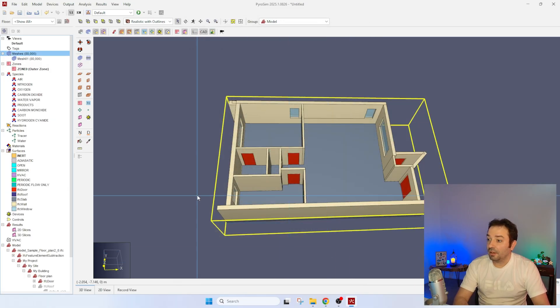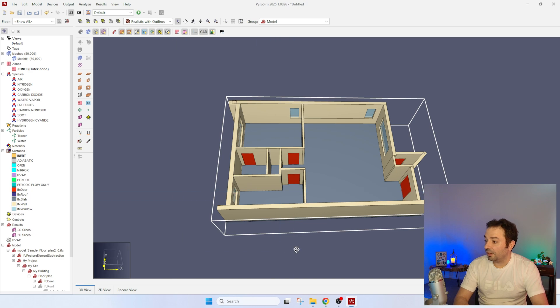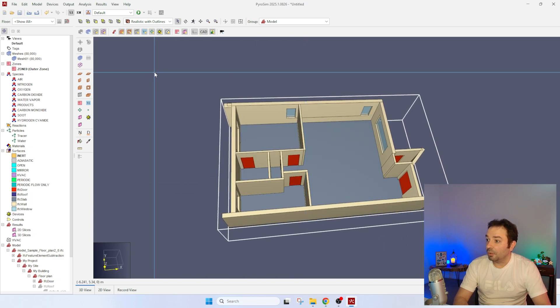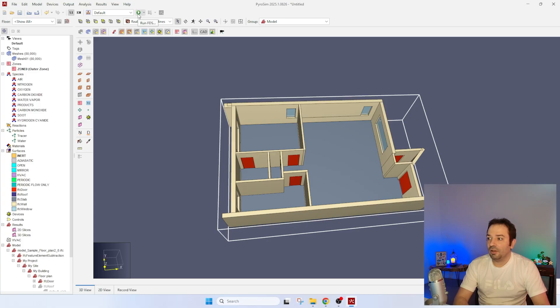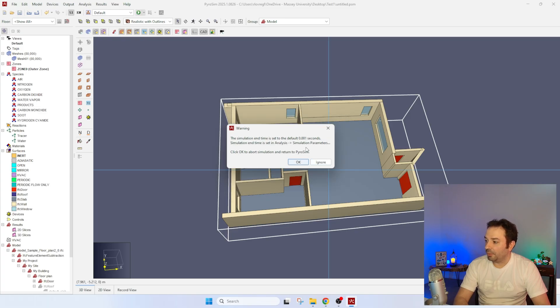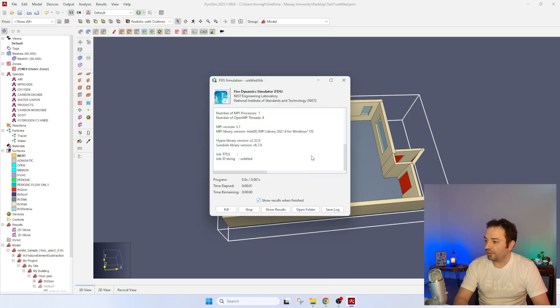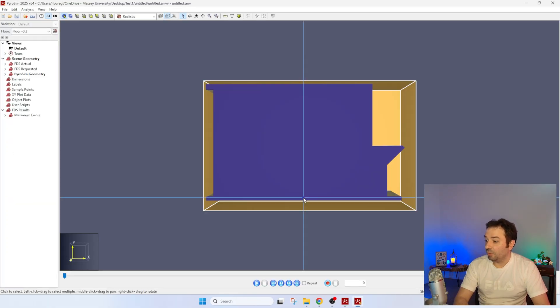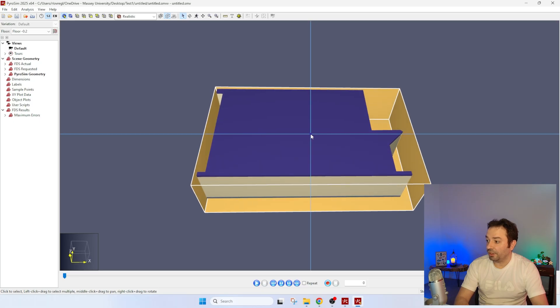I'll press OK and you can see the geometry and the mesh are there. I'm going to try running the simulation without any fire to see what it looks like in FDS. It's spotting issues — the mesh is not open — so we can look at that later. It's also telling me the simulation will run for only 0.001 seconds, so we need to change that if we want a real simulation.